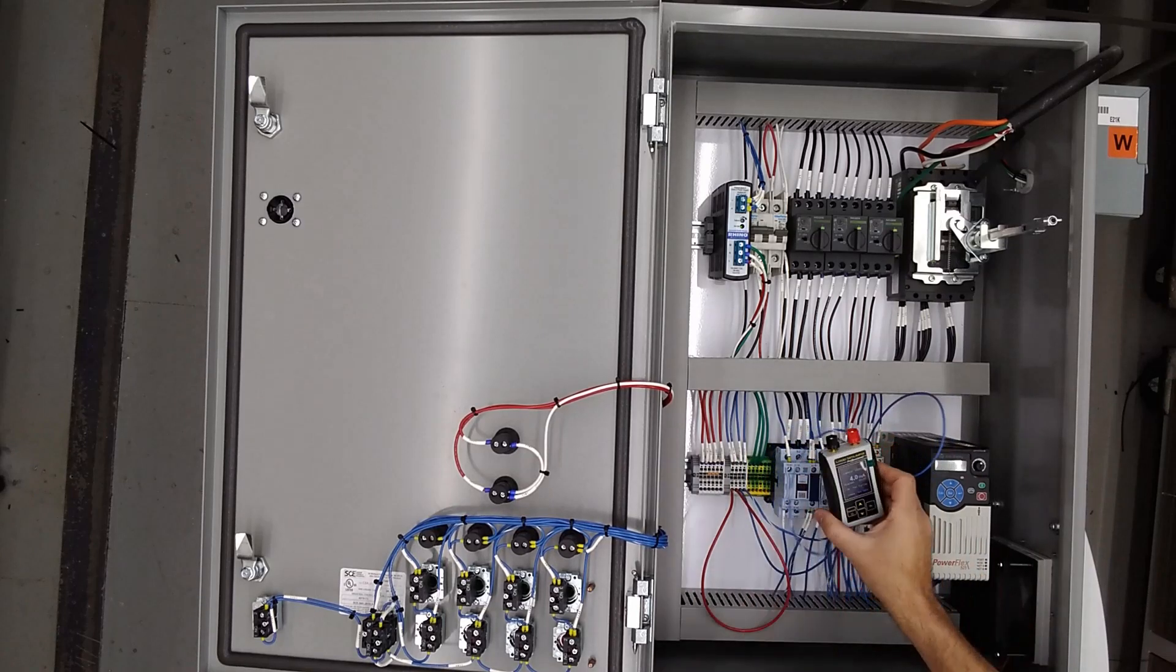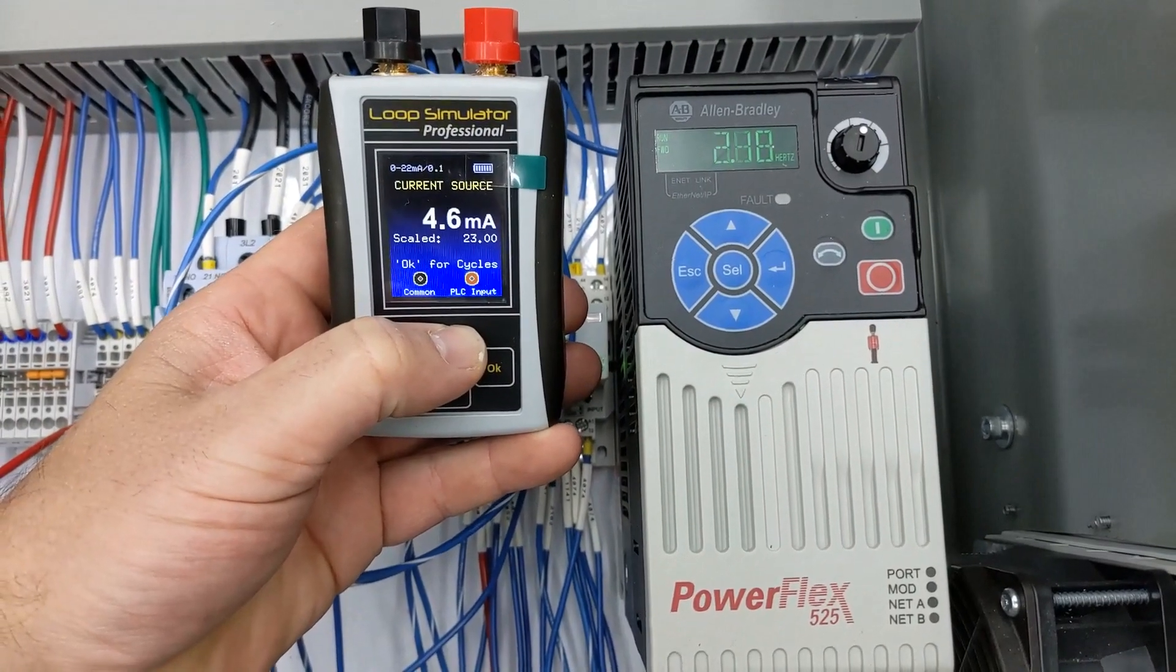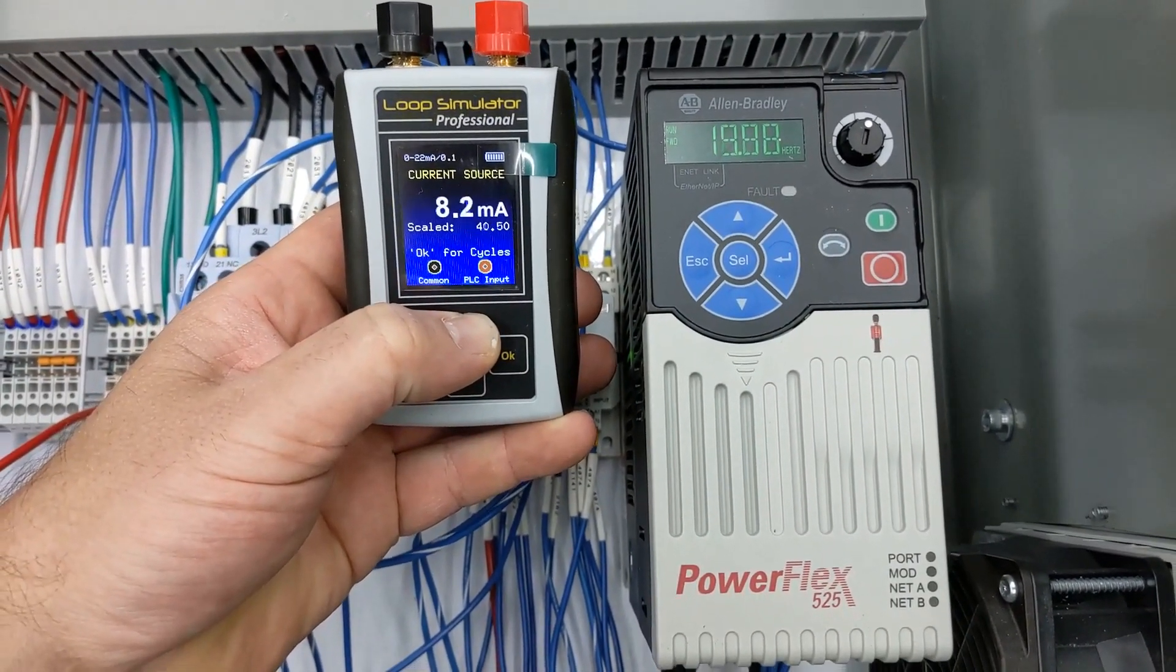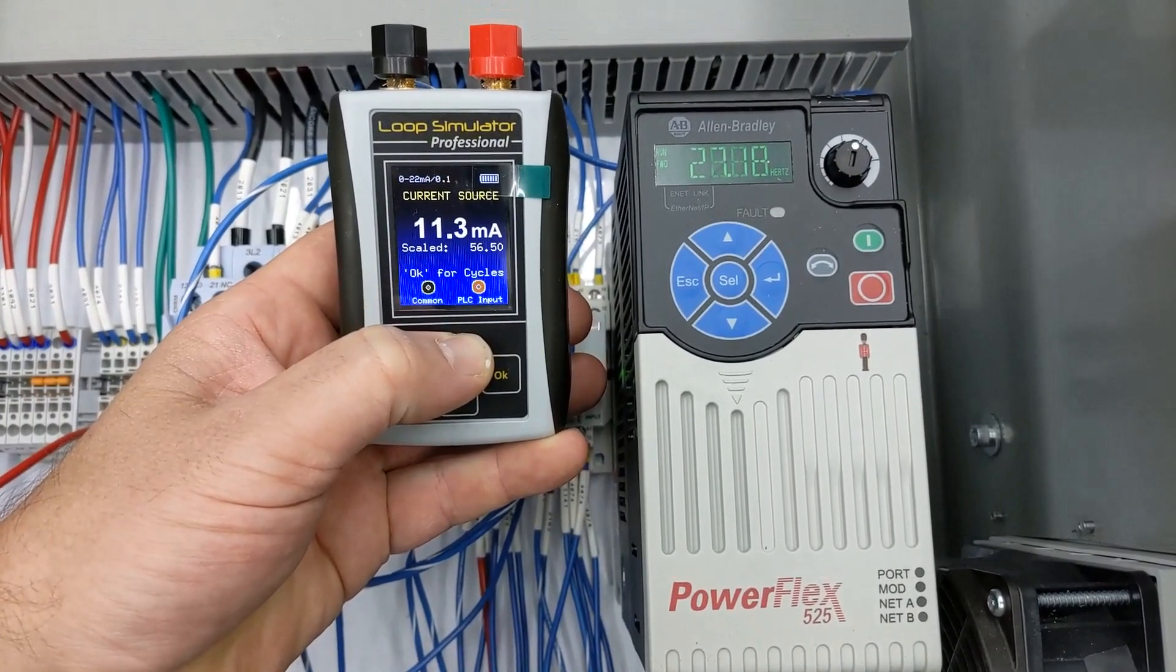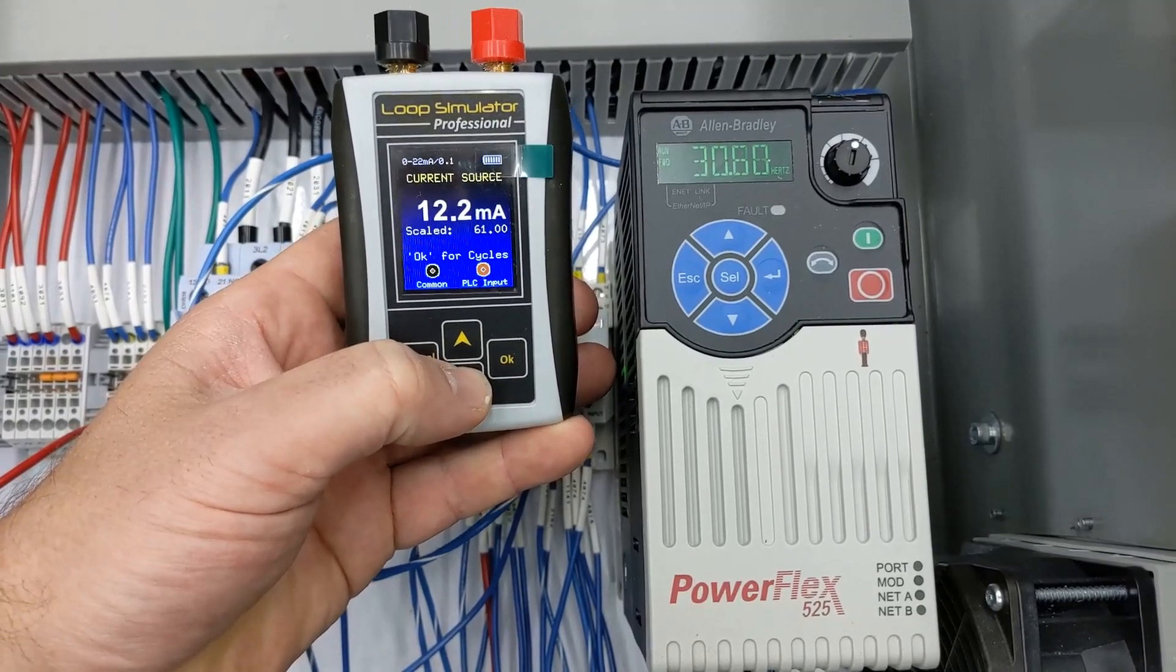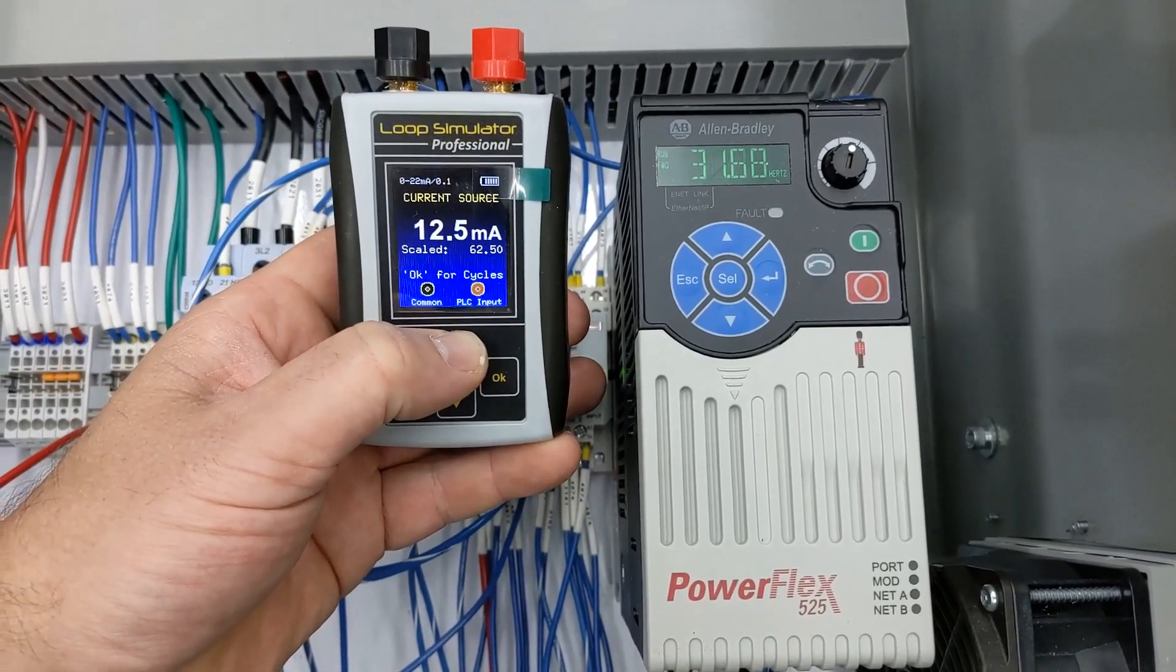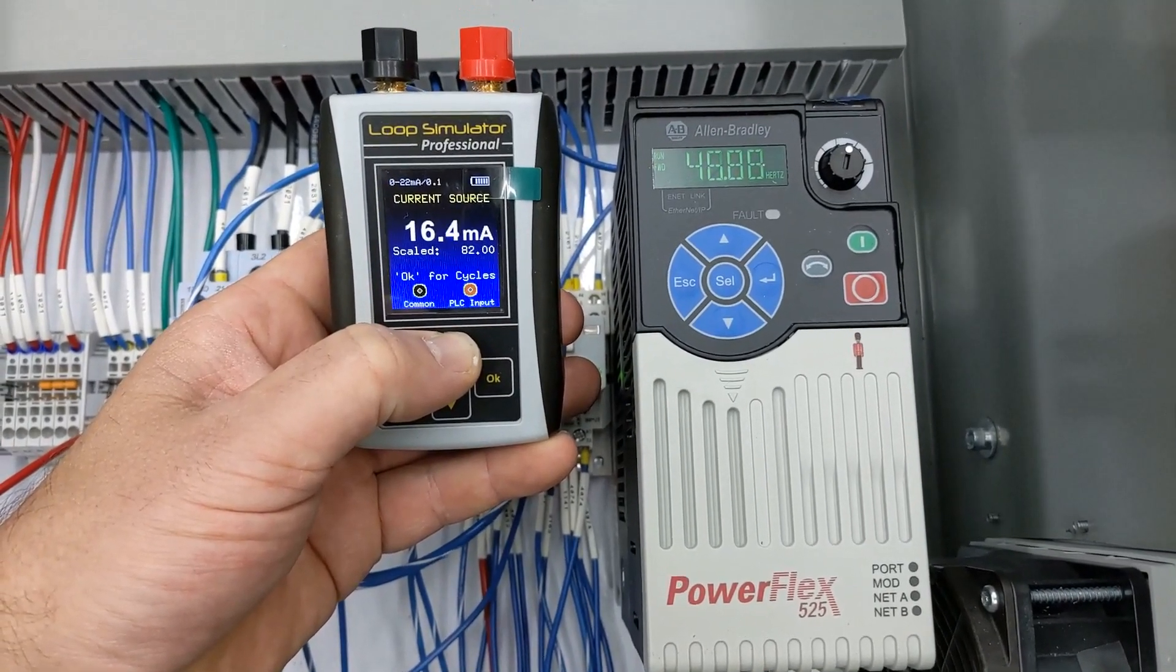Let me get a close-up of this. So four milliamp is going to be zero. And as we go up, you're going to see the hertz on the drive go up. And if we stop around 12, we should be about 30 hertz. And we're roughly 30 hertz. And 20 milliamp will be 60 hertz.